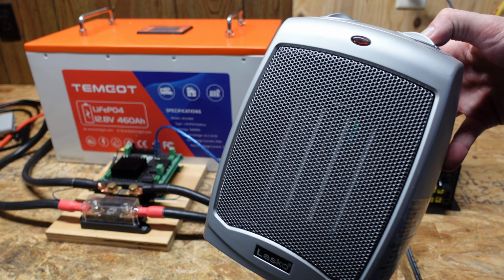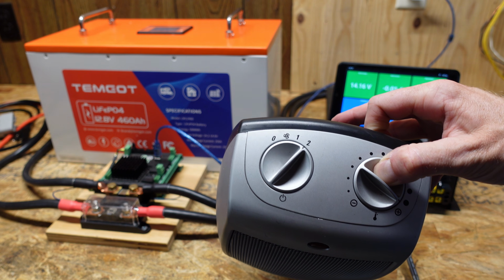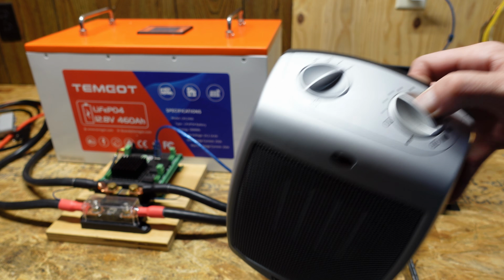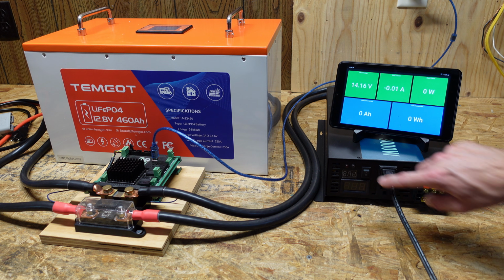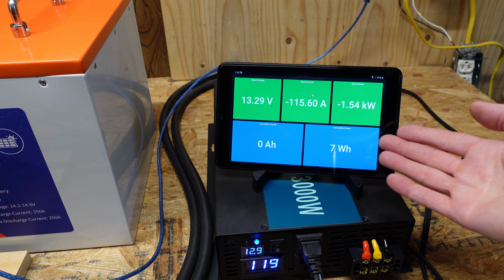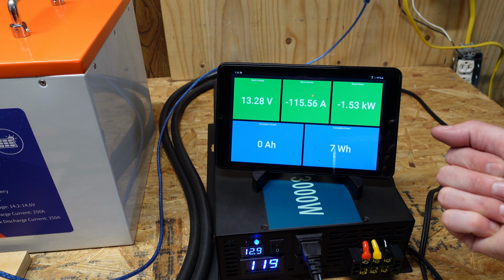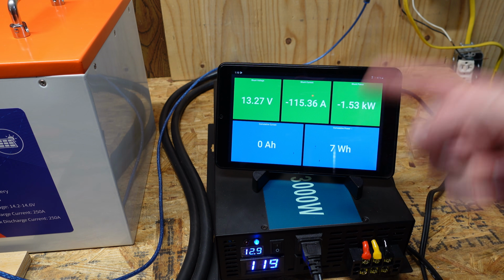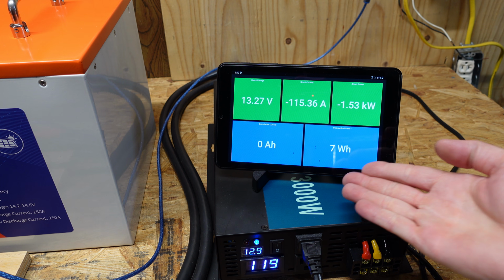The test load will be this Lasko space heater here, and I do have it set on high, which should pull, I'm hoping, around 100 amps or so. So here we go. Looks like we're sitting around 115 amps or so there, so we'll just leave this run until the BMS shuts down our test, then we'll see what our reported capacity is.